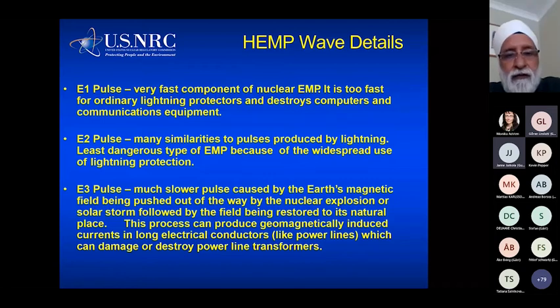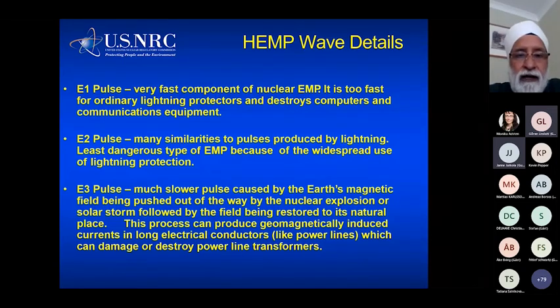So E1, a little bit more detail on E1. Very fast component of the nuclear EMP. It is too fast for ordinary lightning protectors and destroys computers and communications equipment. Too fast. It's gamma rays, essentially. E2 pulse, many similarities to pulses produced by lightning. So it's the least dangerous type of EMP because of the widespread use of lightning protection. So we are familiar with E2 type of pulses.